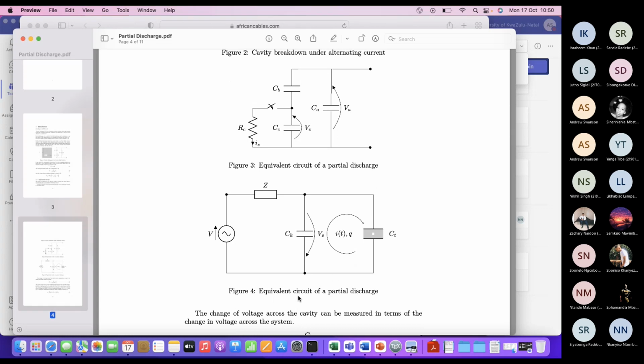So if you look at the equivalent circuit for measuring partial discharge, on your right is a piece of insulation with a little cavity in the middle. We've got a voltage source, an impedance, and what we call a coupling capacitor. As soon as there's a little discharge there, there's going to be a current in our circuit. So that discharge Q is going to give us a current in the circuit. That's cool. That means we don't have to go and see what's actually going on in there. It's internal to that, and we can measure it externally with the circuit.